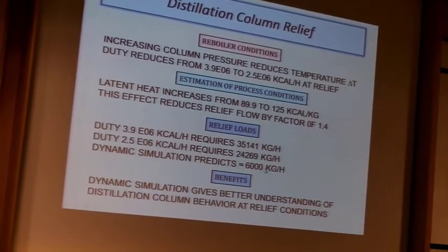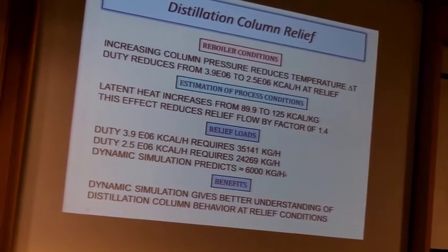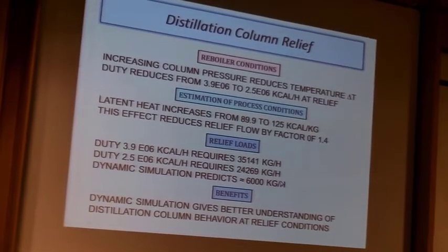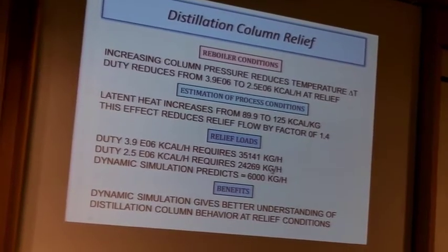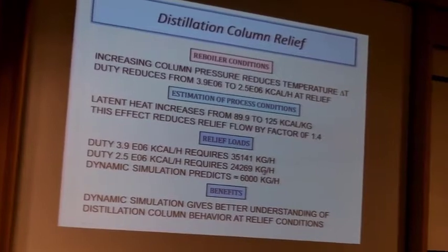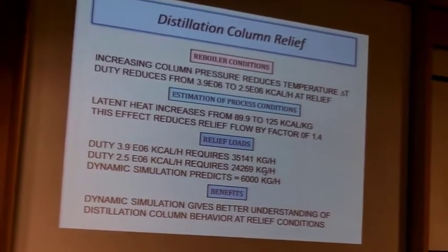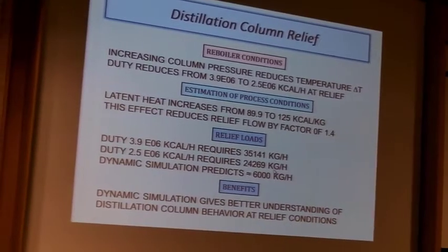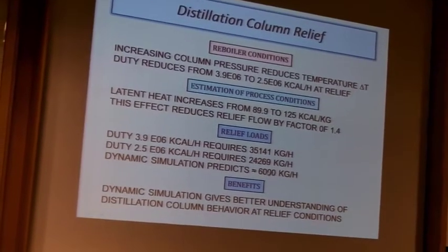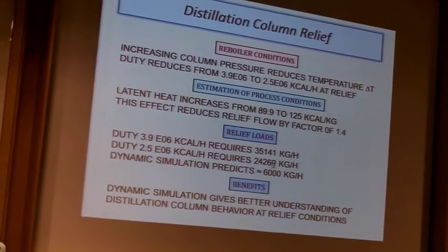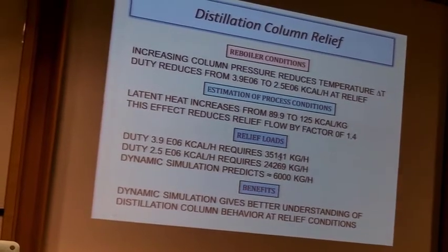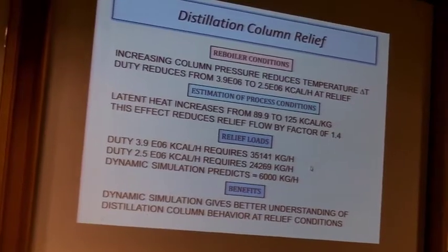And yet the simulation's predicting 6. I'm not saying I would size the relief valve at 6, but it would certainly start me thinking about the difference between an 8-inch relief valve and a 6-inch relief valve and a 4-inch relief valve with some confidence. That would need a 3-inch relief valve. That needs a 6-inch, and that needs a 6-inch. A different trim.